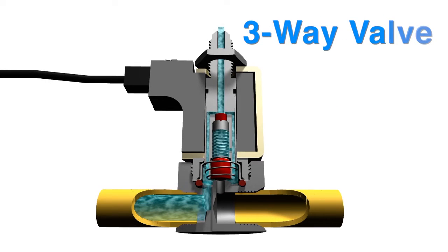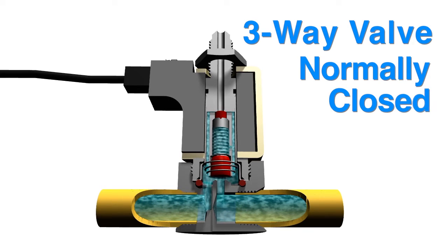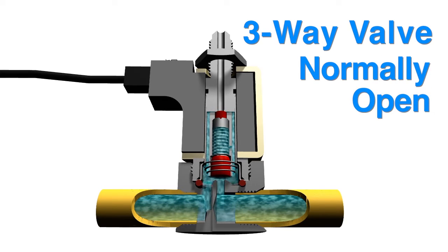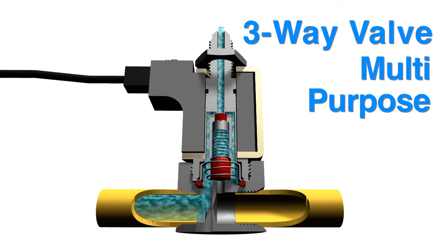A three-way solenoid valve has three pipe connections and two orifices, one of which is always open, allowing for two paths of flow. There are four common types of three-way solenoid valves: three-way normally closed, three-way normally open, three-way directional control, and three-way multipurpose.